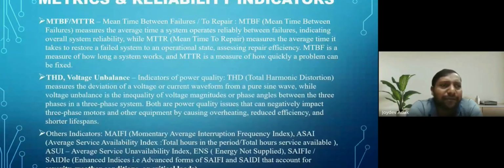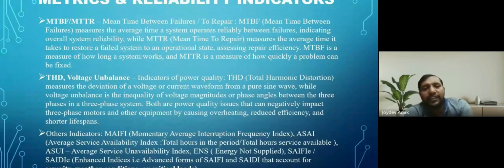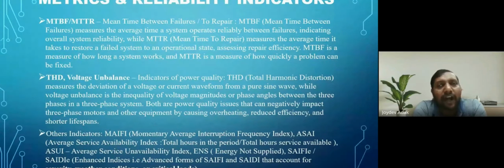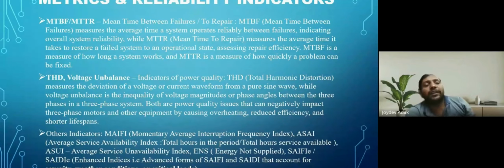Now MTBF and MTTR. MTBF is the mean time between failures. If tripping is occurring in the system, the time between two failures is the MTBF, mean time between failures. It means how long the system or utility is available for the consumer. And MTTR is the mean time to repair. So how much time does it take to restore the system? Between failure and repair, how much time does it take?